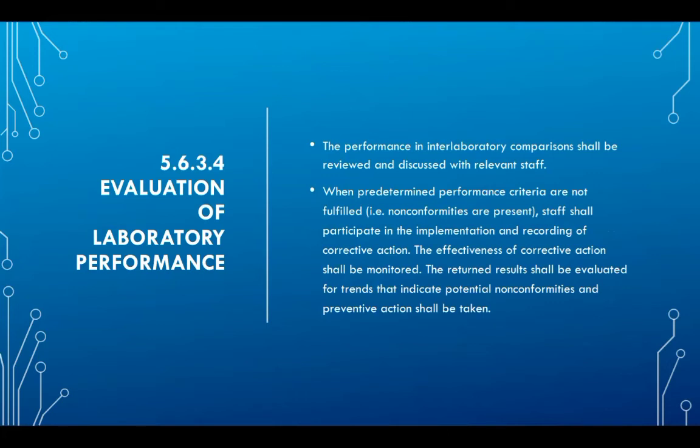And you shall have predefined performance evaluation criteria, maybe Z-score or something else. And whenever you find this predefined criteria is not met, you are discussing with your colleagues, with your lab people, and after root cause analysis, taking appropriate action. And you are monitoring the effectiveness of this corrective action. In the next cycle, that problem shall not happen again.